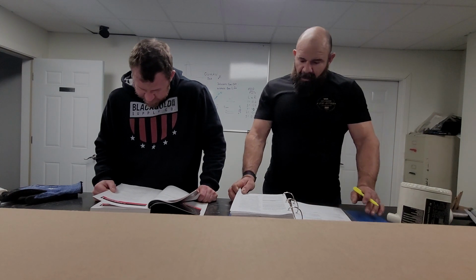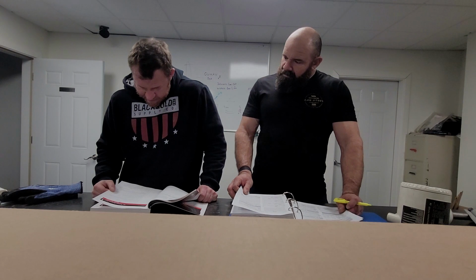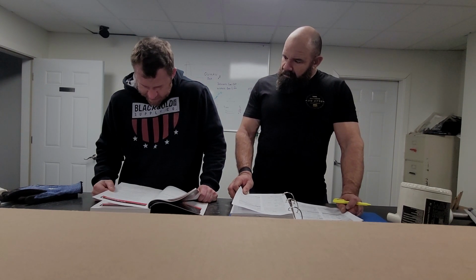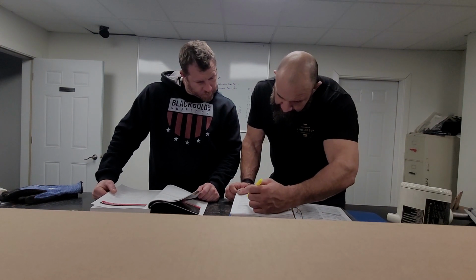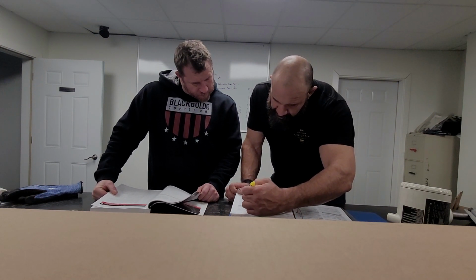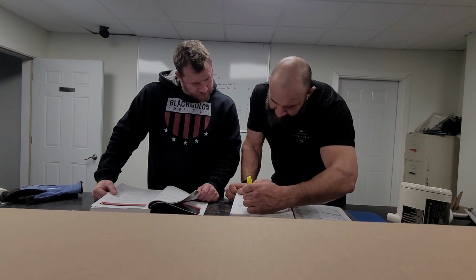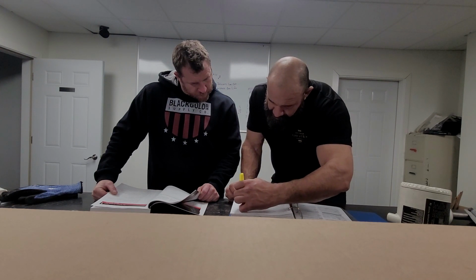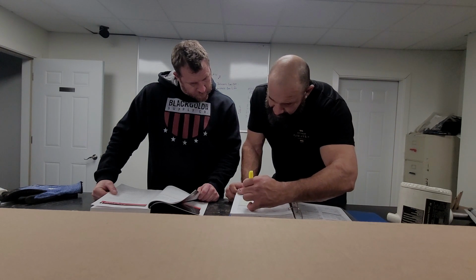Chapter blank of the NEC is independent of other chapters, and none of the provisions apply unless they're directly referenced. That's chapter 8, which deals with communication equipment and stuff. Next: equipment designed to open circuits under fault conditions shall have an interrupting rating not less than the available voltage and circuit current at the line side of the equipment. True or false? True. Where'd you find it? It would be in here, the definition of circuit breaker: designed to open and close a circuit without damage to itself when properly applied within its rating.